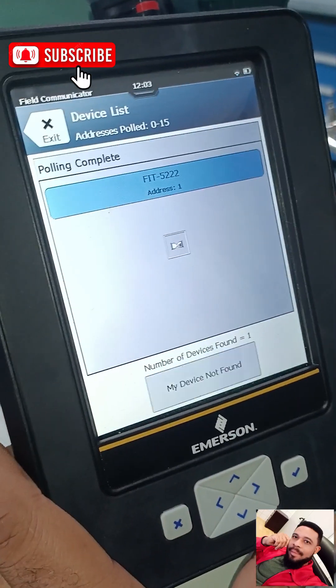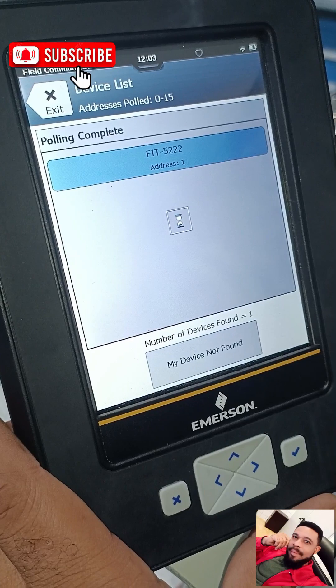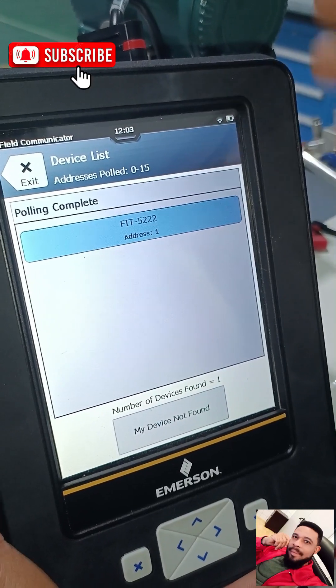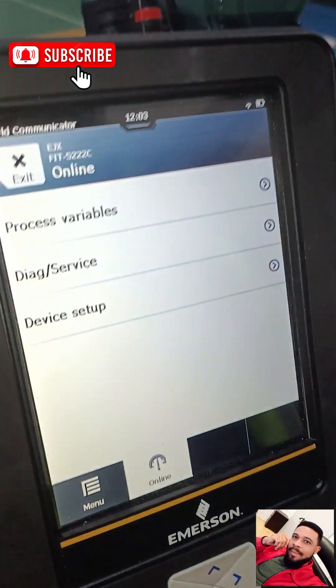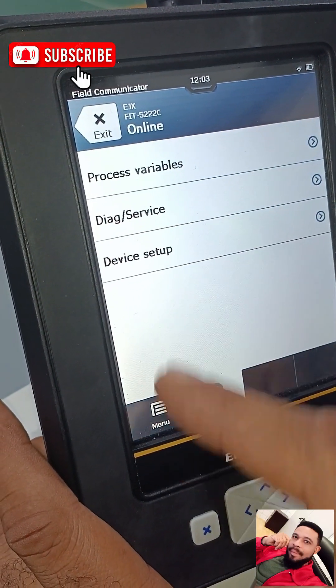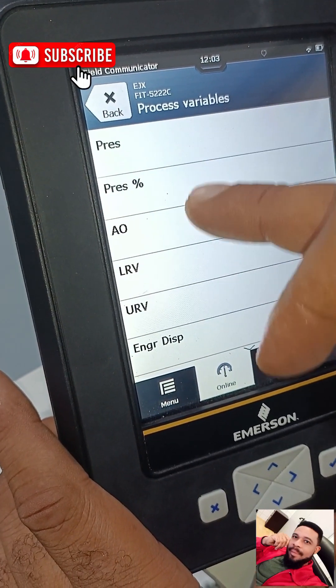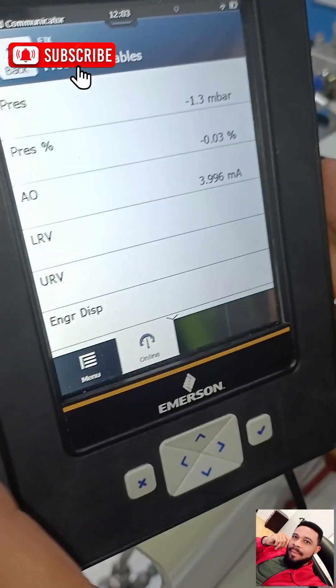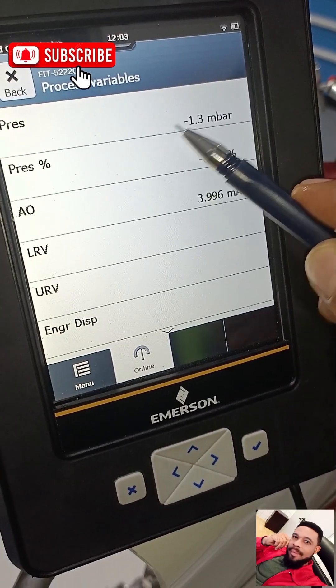We give it some time — polling complete. Now you can see the display blinking, which tells you that our Trex device is trying to establish a connection with the transmitter. Now it's fully connected. We can see Process Variable, Diag Services, and Device Setup. We go to Process Variable and can see pressure, pressure percentage, AO, lower range, and upper range. We have successfully connected our HART Trex device to the transmitter.